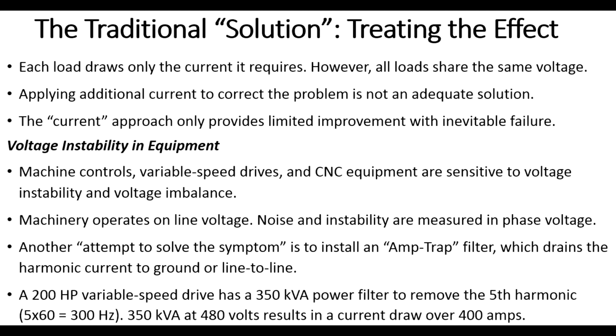Now, current is going to be drawn based on each load's impedance, the magnitude of the load or the impedance of the load. So if you have current in one part of a facility causing electrical noise that affects equipment in the other part of the facility, drawing more current when you have a current problem is not an efficient method of trying to solve that, because everything shares the same voltage. The currents are individual. For example, you have a circuit breaker that feeds one circuit, you have another circuit breaker feeds another circuit, and from your load center in your house, for example, there's many different circuits, and each circuit draws its own current.